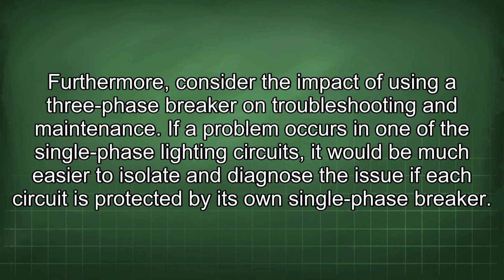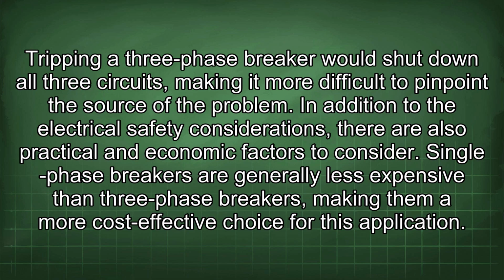Furthermore, consider the impact of using a three-phase breaker on troubleshooting and maintenance. If a problem occurs in one of the single-phase lighting circuits, it would be much easier to isolate and diagnose the issue if each circuit is protected by its own single-phase breaker. Tripping a three-phase breaker would shut down all three circuits, making it more difficult to pinpoint the source of the problem.